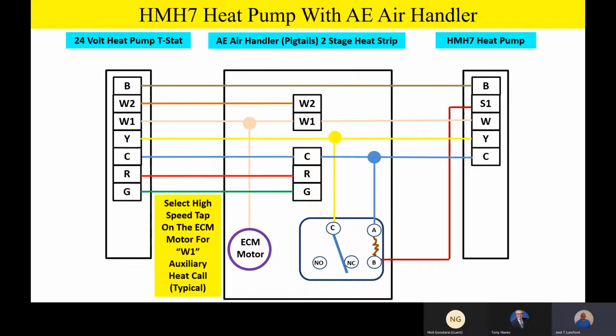One of the things we always want to remember on a heat pump application, if we do have heat strips, or even if it's a straight cooling application and we're going to have a heat strip in the air handler, is that we're going to want to take W1 from the heat strip, or that auxiliary heat call, and take it to the high speed motor tap on the ECM motor. This is important because when we go into the heating mode of operation, we want to make sure we don't overheat that heat strip or heater kit. So we want to select W1 for auxiliary heat, and typically we'll take it to the high speed tap on that ECM motor.